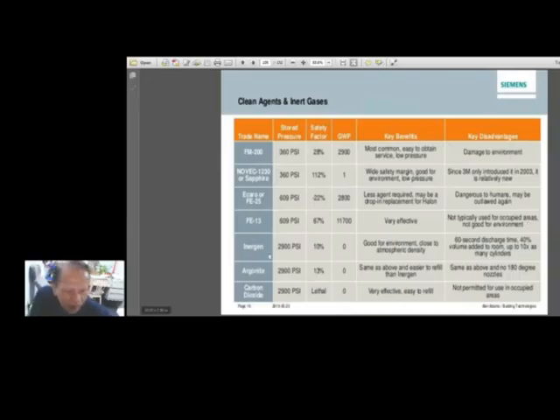Inergen. 2,900 PSI, so very, very high pressure. Safety factor is 10. 0 GWP. Good for environment. Close to atmospheric density. 60-second discharge time. So 1 minute. 40% volume added to room. Up to 10 times as many cylinders. So very bulky. So you need so many cylinders.